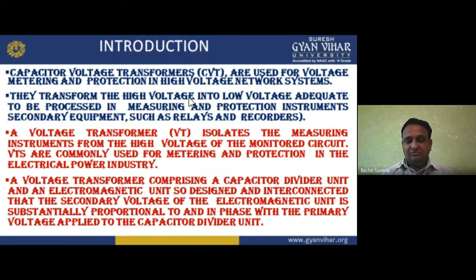Now working. In its most basic form, the device consists of three parts: two capacitors across which the transmission line signal is split, an inductive element to tune the device to the line frequency, and a voltage transformer to isolate and further step down the voltage for metering devices or protective relays. So three things are there. First, the two capacitors unit in a unit. Second is the inductor, and third is the voltage transformer or potential transformer. The potential transformer is basically for protection or metering, and the capacitor and inductor are for the line frequency. We have a tuned circuit for the line frequency.